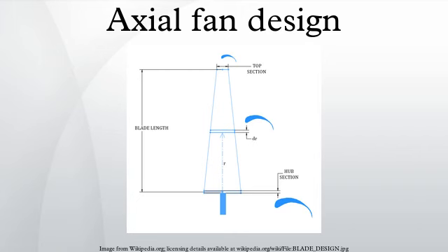The pressure variations to the left of the point S cause unsteady flow, which is due to the two effects of stalling and surging. Causes of unstable flow: stalling and surging affect the fan performance, blades, as well as output, and are thus undesirable. They occur because of improper design and fan physical properties, and are generally accompanied by noise generation.